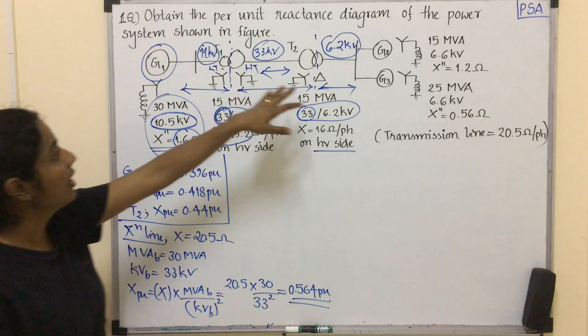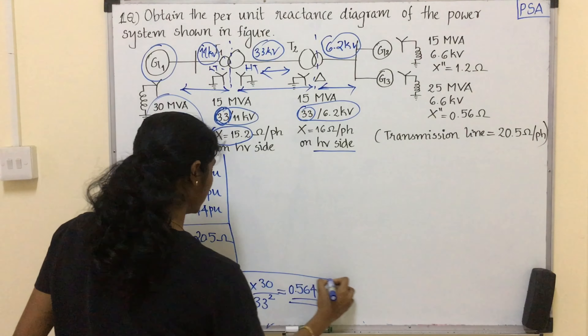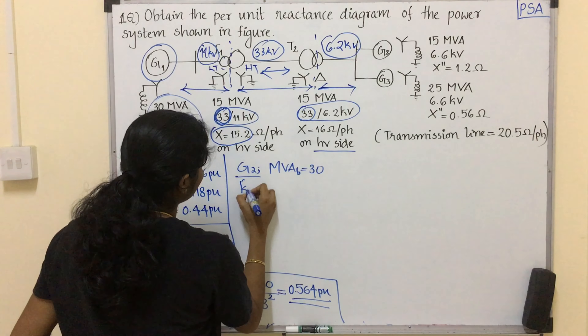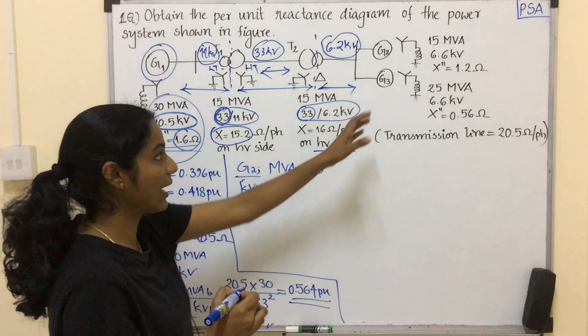Now let's see generator G2. For generator G2, MVA base equals 30 and KV base equals the base value for this region, which is 6.2 kV. The sub-transient reactance is 1.2 ohm. So X per unit equals 1.2 multiplied by MVA base 30 divided by KV base squared, which is 6.2 squared. The value will be 0.936 per unit.